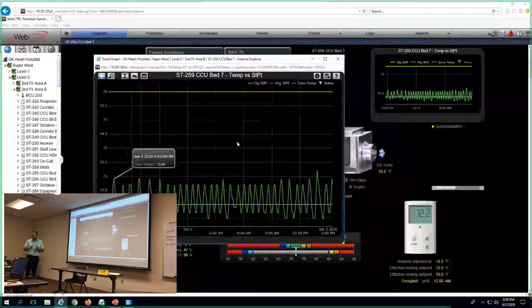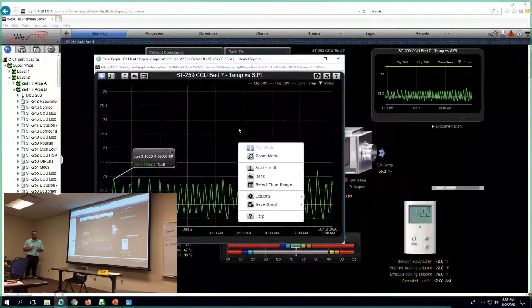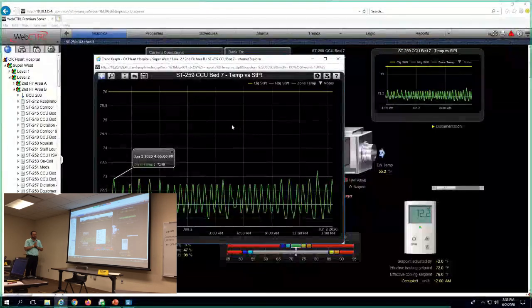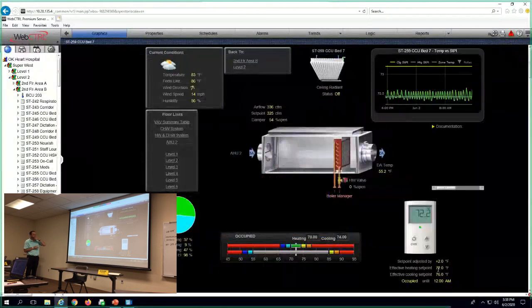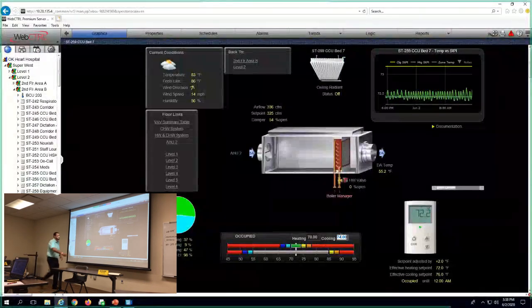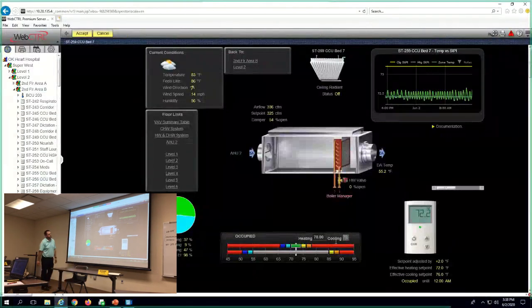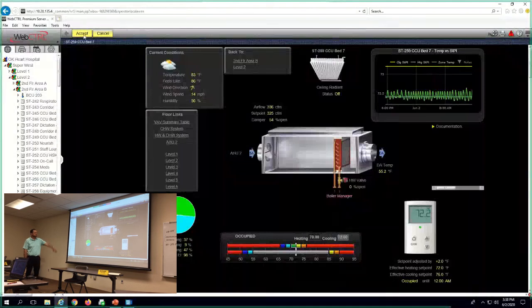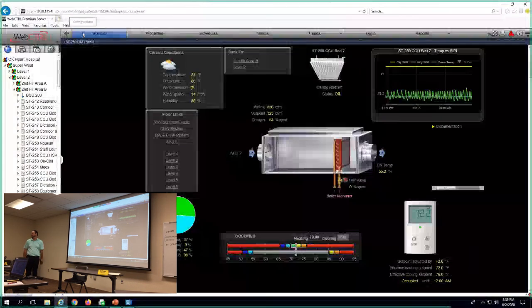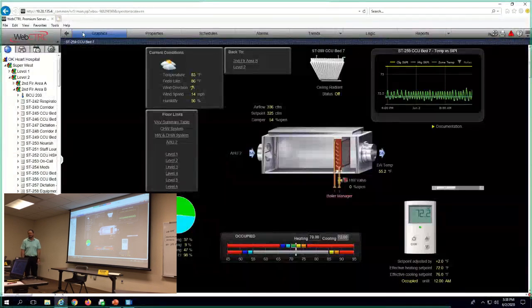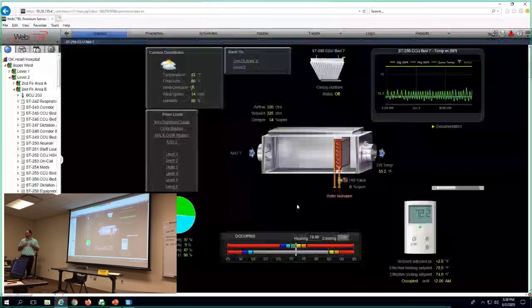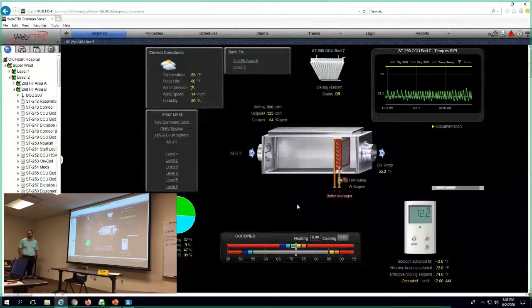Any questions on the set points or the colors or any of that? If we go in and change that, the cooling set point, is that on the actual bar trend on the bottom? That shows us it says heating 70 and cooling 74. Okay, click on the X right down here at the bottom. Yeah, click right here, click on the 74, make it 72. Already got it on the set. And hit save. It's done. Now you made it 2 degrees different. It's easy to change them. That's why I was saying globally, we can change a lot quickly.